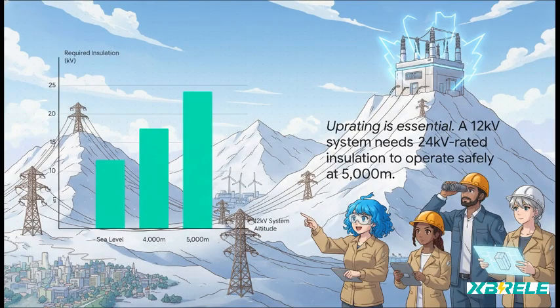Here's what that oversizing strategy looks like for voltage. A system that just needs 12 kilovolt insulation at sea level, well, at 4,000 meters, needs insulation rated for 17.5 kilovolts, and at 5,000 meters, a whopping 24 kilovolts. You're basically buying insulation for a much more powerful system just to get reliable performance.